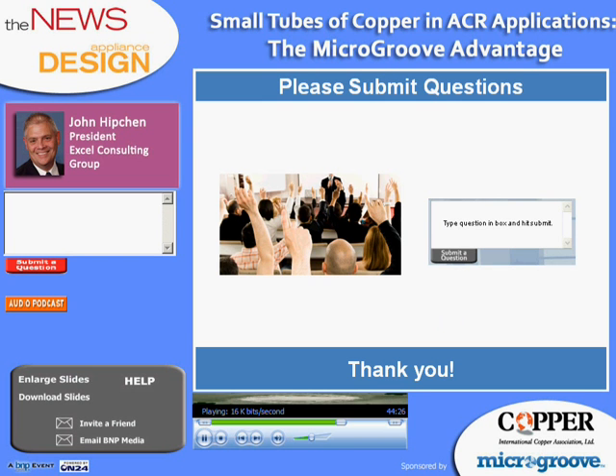Okay. Another question comes in from Mr. Chuck Hosen and wants to know if the microtube diameters are standard. For instance, is it considered microtube if it's 5 or 4, or is there any particular increment of diameter that classifies itself as microtube? Not at this point, Mike. Microgroove just refers to smaller diameter tubes, probably 7 millimeters and lower. It definitely refers to a move off of the traditional 3/8 inch or 9.52 millimeter tubes.